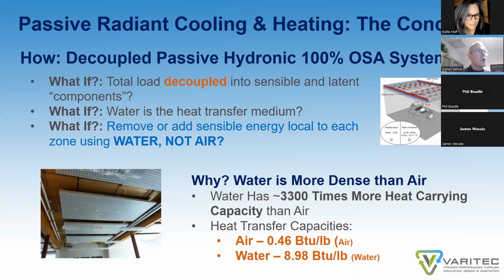So instead of the total load being seen at a cooling coil in an air handler mounted on the roof, what if we decouple the total load into its sensible and latent components? What if water becomes the heat transfer medium for the sensible load? What if you remove or add sensible energy local to each zone and not air? Well, why would you want to do that, and what advantage does it hold?